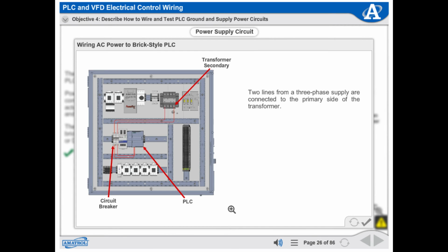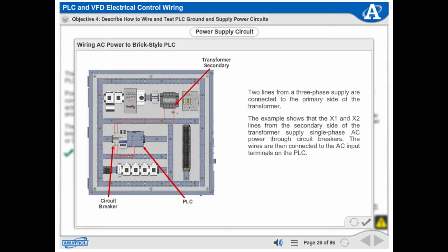Two lines from a three-phase supply are connected to the primary side of the transformer. The example shows that the X1 and X2 lines from the secondary side of the transformer supply single-phase AC power through circuit breakers. The wires are then connected to the AC input terminals on the PLC.